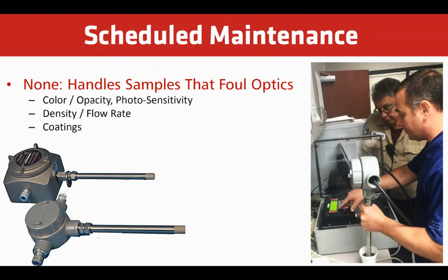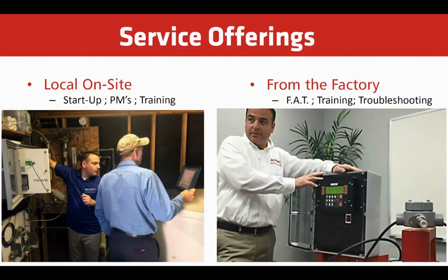Really no maintenance on this device compared to an optical. There's no color or opacity interference because it is acoustic. It will not affect any photosensitive samples, whereas if you're always shining a light, that can be an issue for certain customers. It does not really care about the density of the sample or the flow rate. And again, it is impervious to coatings affecting the results. Obviously, with any of our galvanic products, we offer local and on-site startups and training, and FATs at our factory.